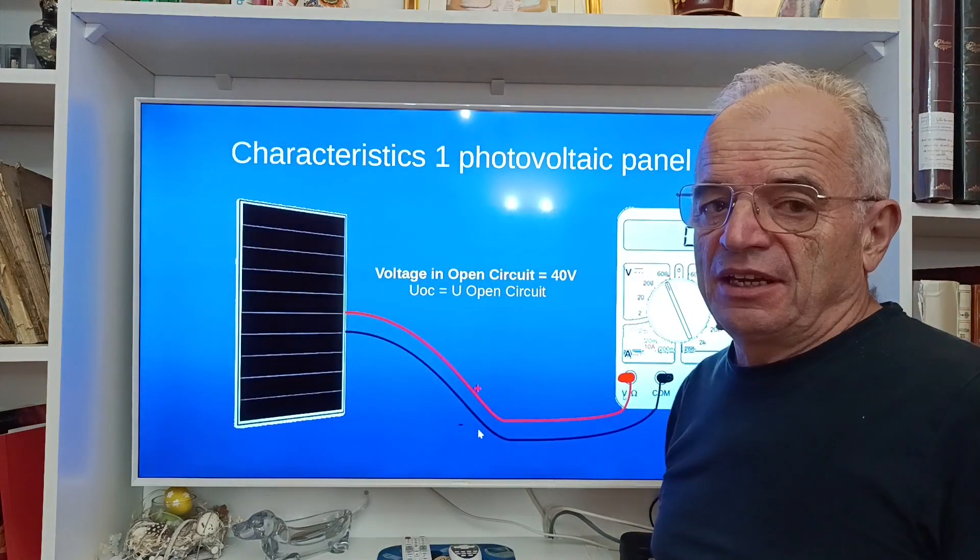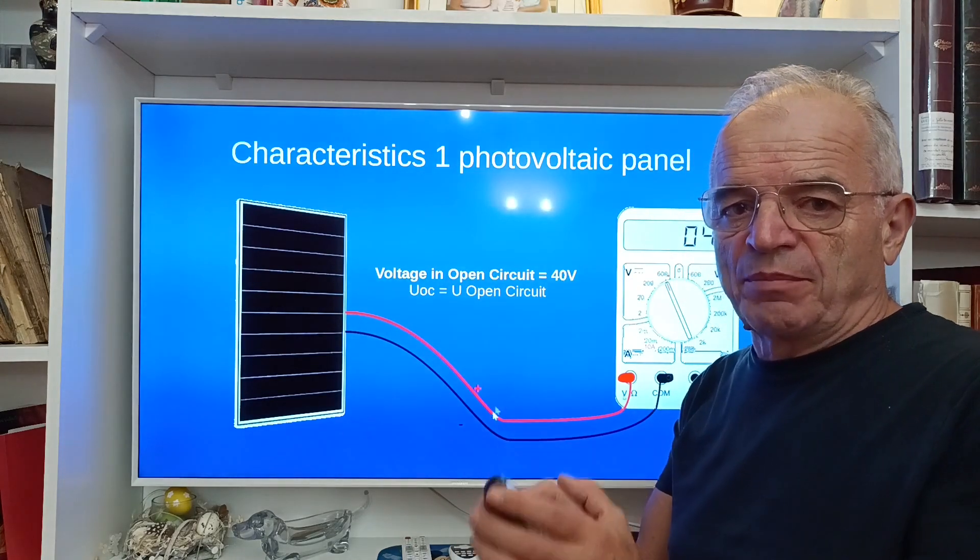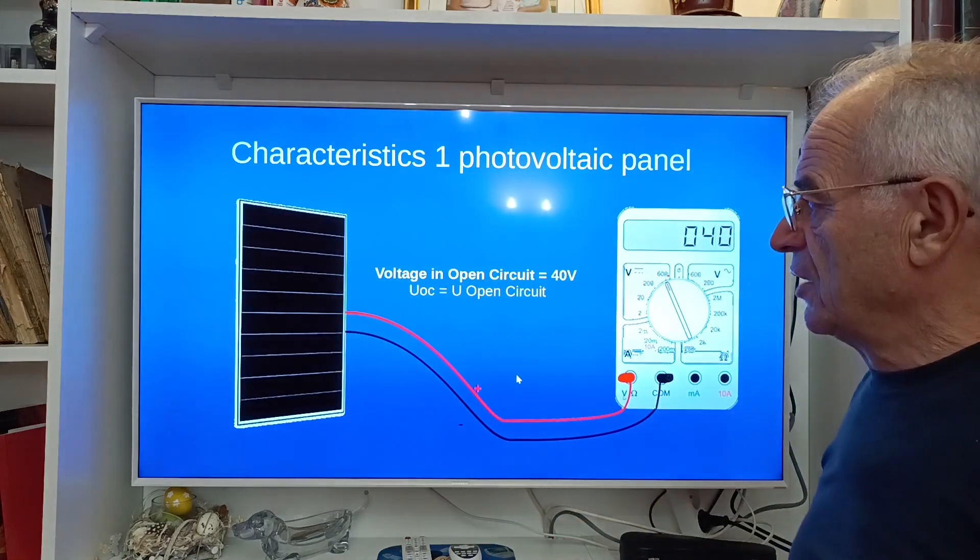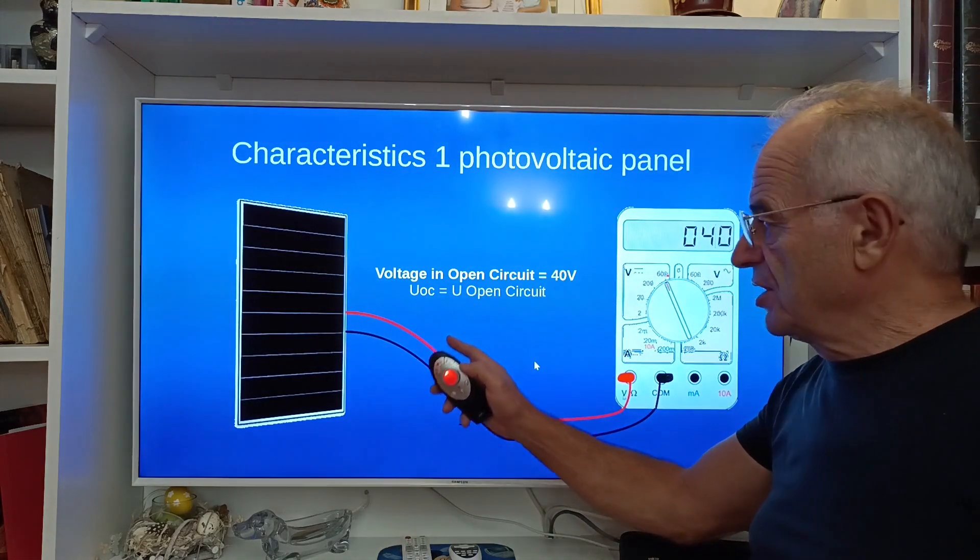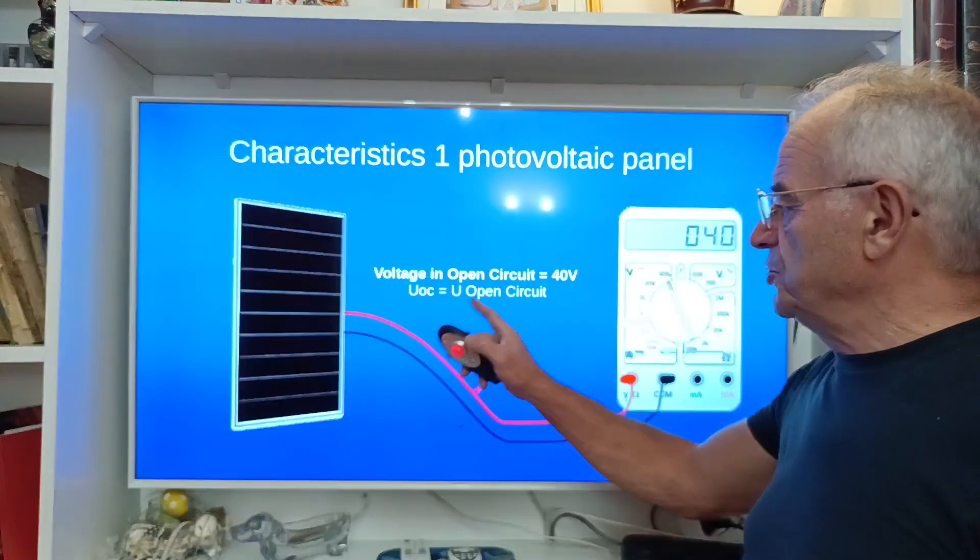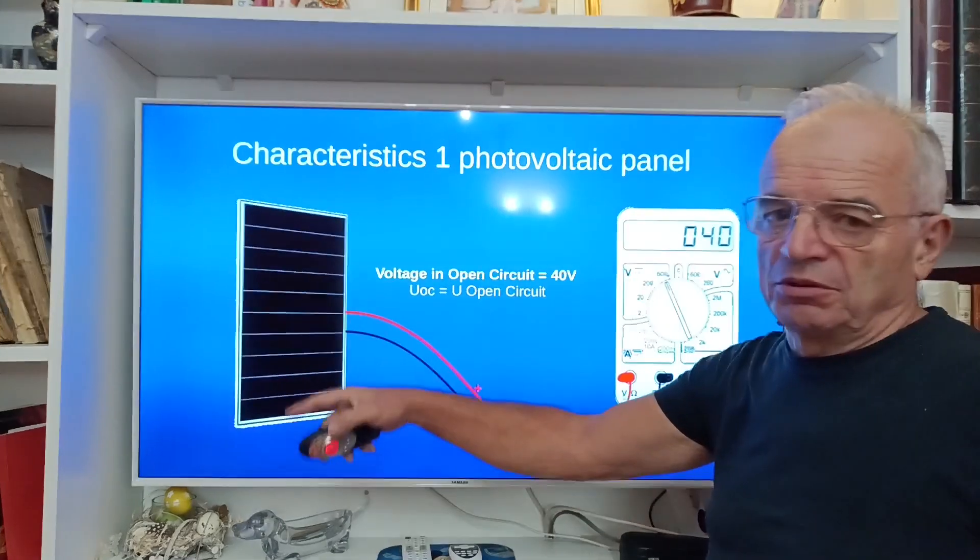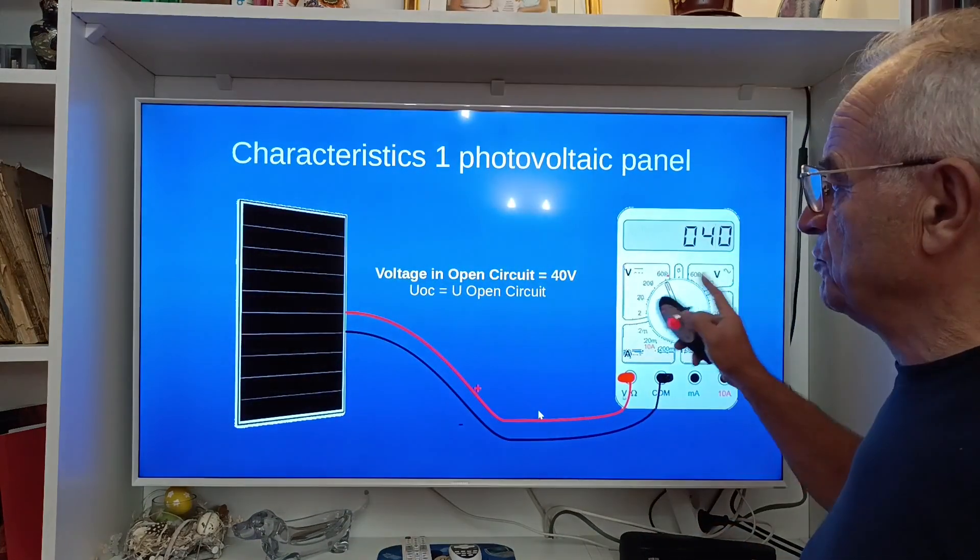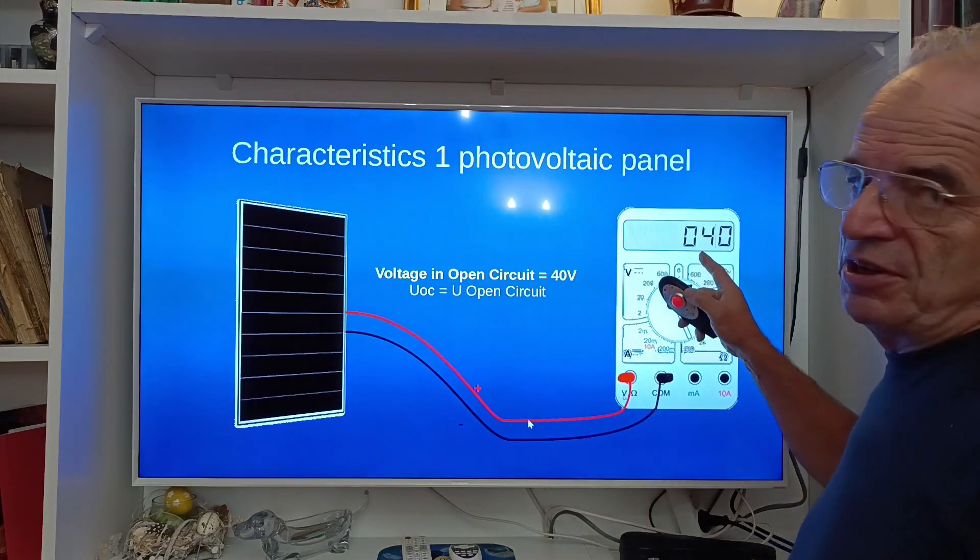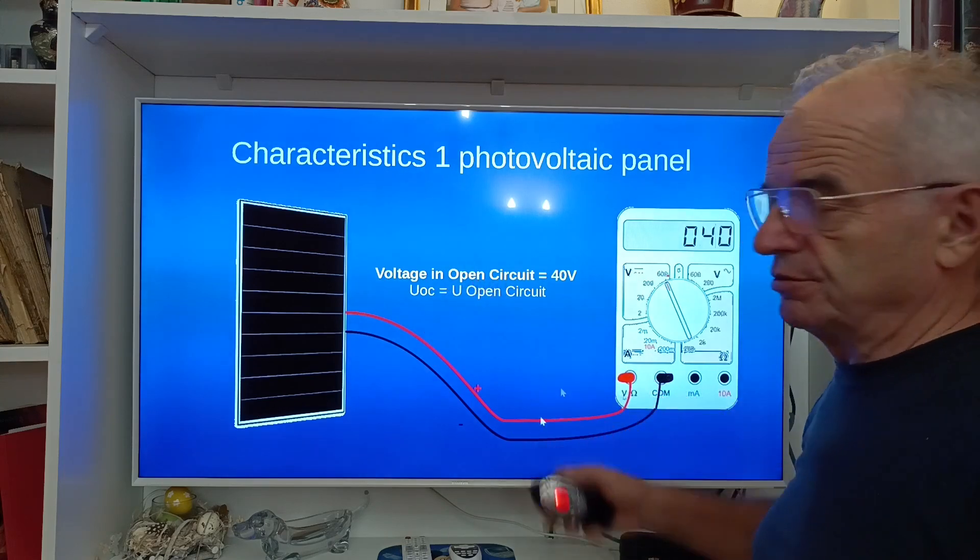The first point is to see the characteristics of just one solar panel alone. One main characteristic is what we call the open circuit voltage, also called U open circuit. For example you put a panel like this one, a big one around 400 watts, and you connect a voltmeter and here you have 40 volts of voltage in open circuit.